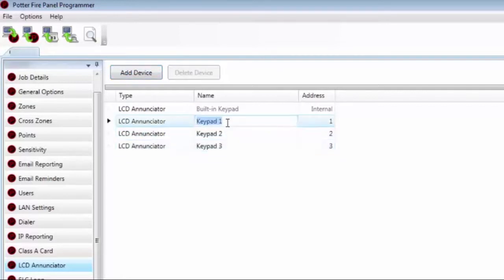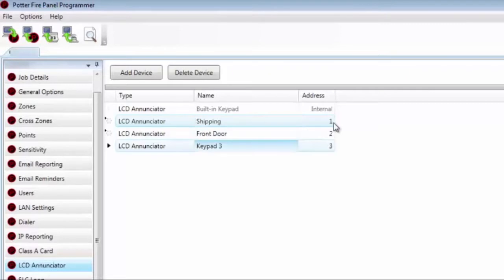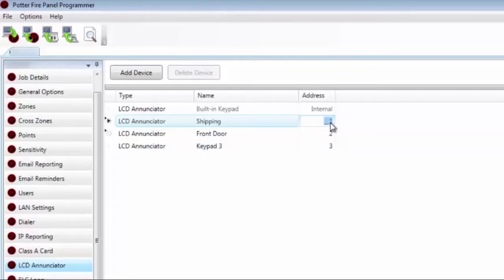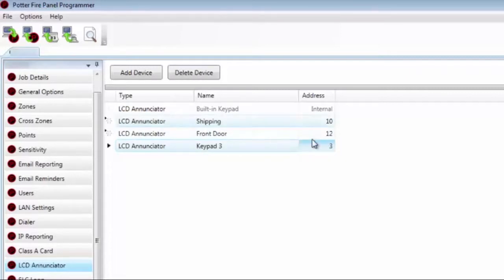You can edit the Name field to give each annunciator a descriptive name. This name will not show up on the LCD screen of the remote annunciator, but it will help with troubleshooting if there is ever an issue. The address shown in the right-hand column corresponds to the DIP switch setting on the back of the annunciator. It needs to be some number between 1 and 31. You can go out of order — for example, you could start with address 10, then 12. It doesn't matter, just some number between 1 and 31.